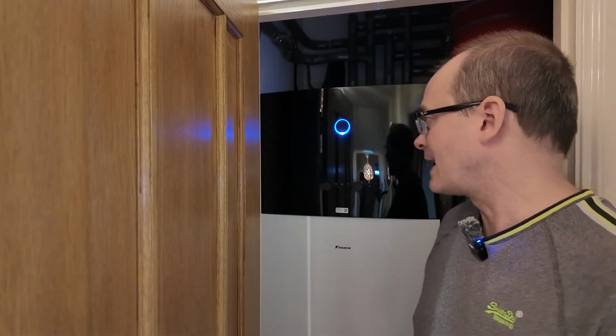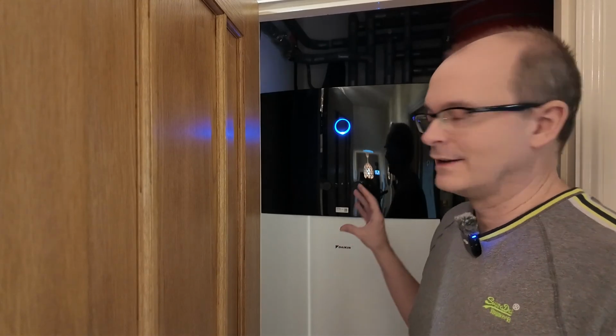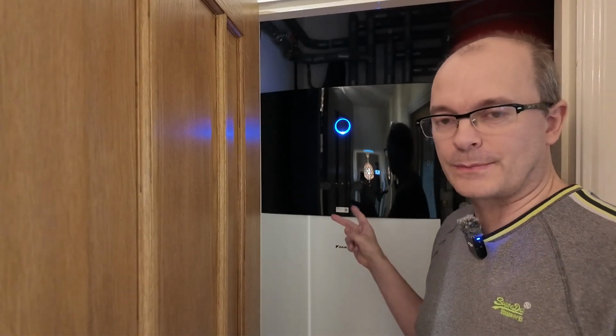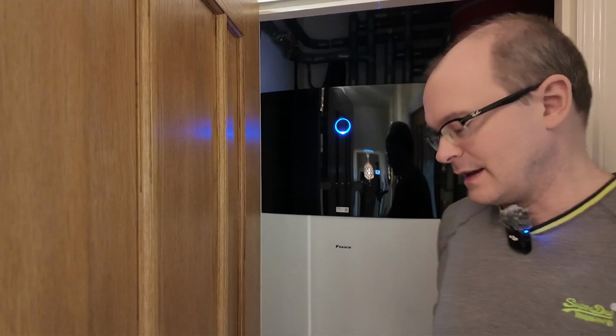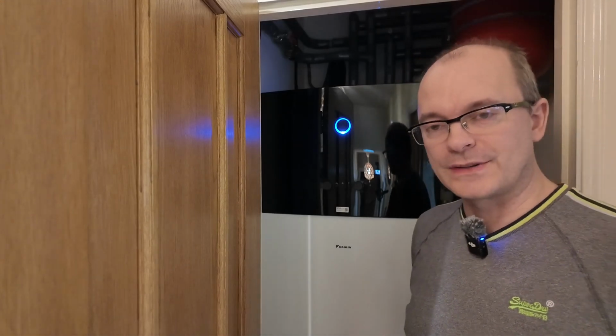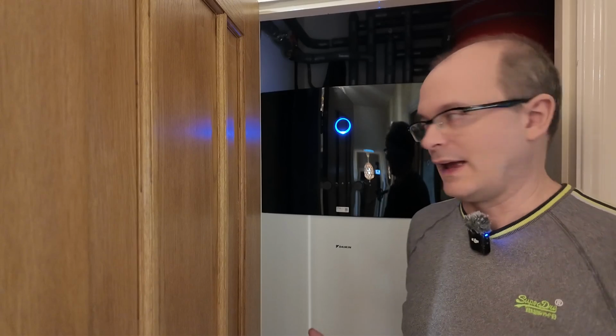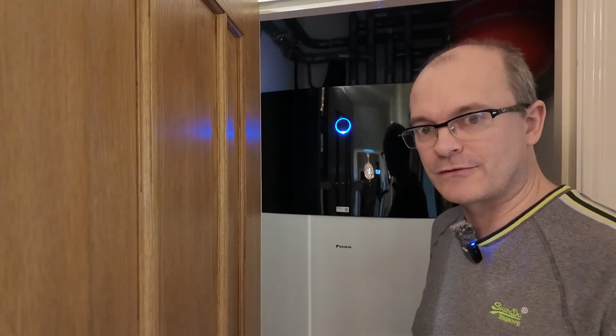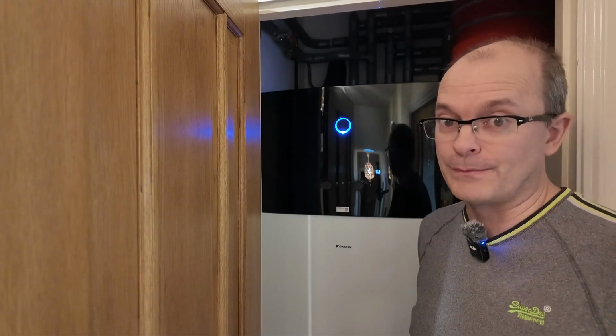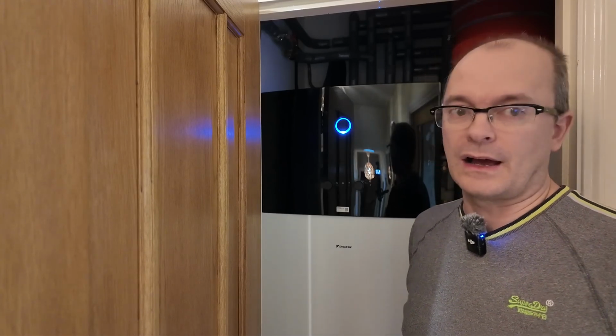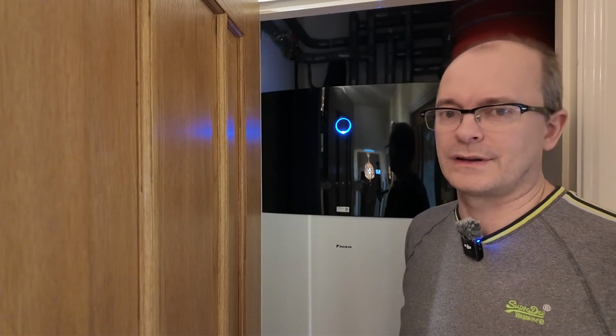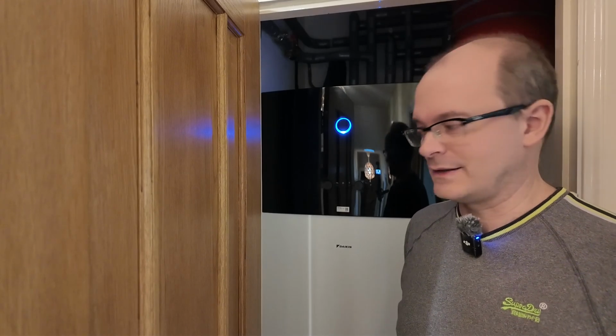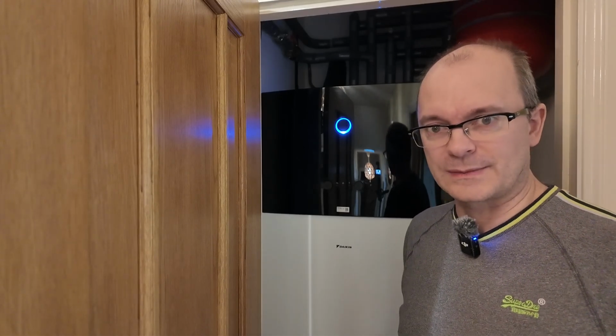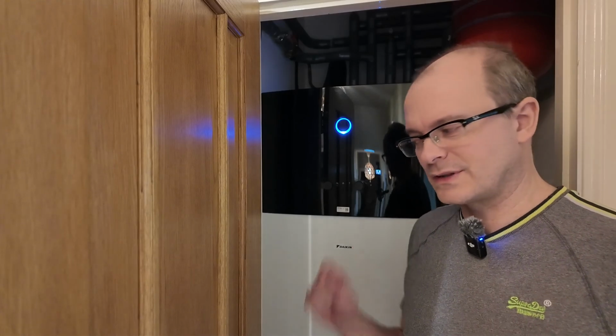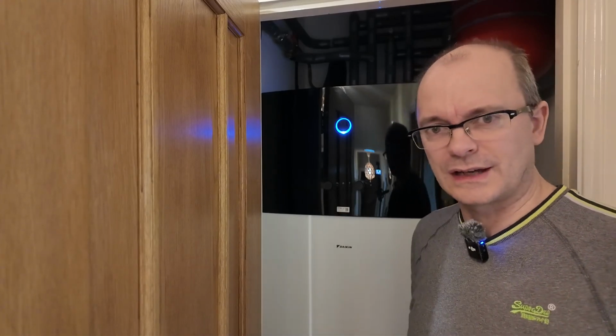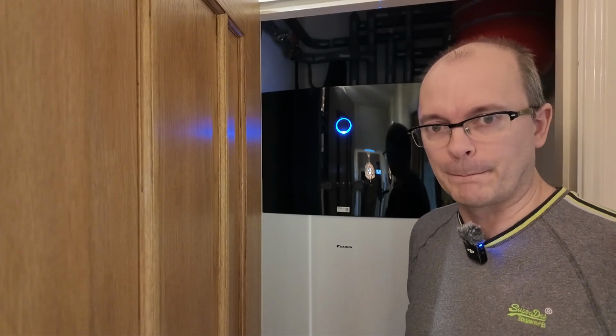Now, I do think that Daikin should update the configurable options on this by virtue of a firmware update. It should be possible to have a different weather compensation curve for holiday mode. After all, I still want the heat pump to run efficiently when I'm not at home. In that particular day, I was using about 15 kilowatt hours to run the heat pump, and that drained the battery during the expensive part of the day. So I was almost using expensive electricity even though I wasn't at home.